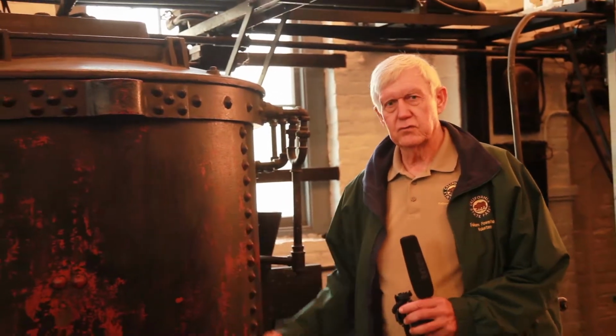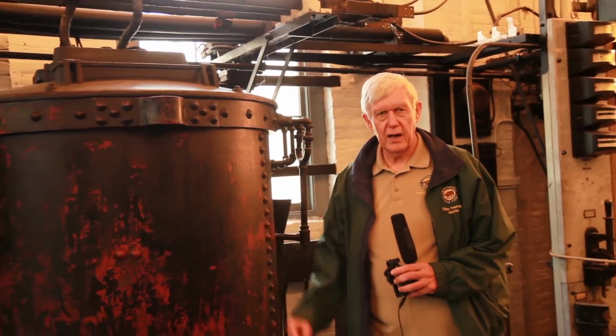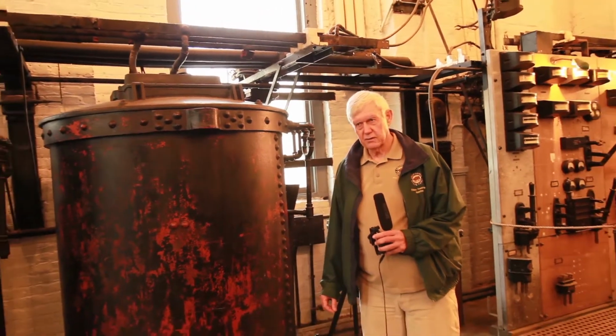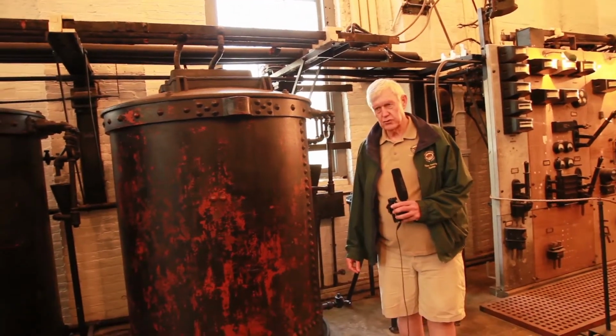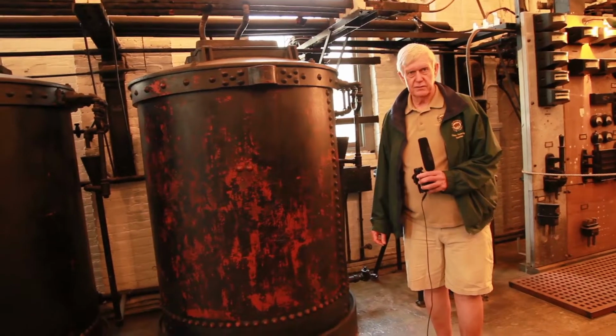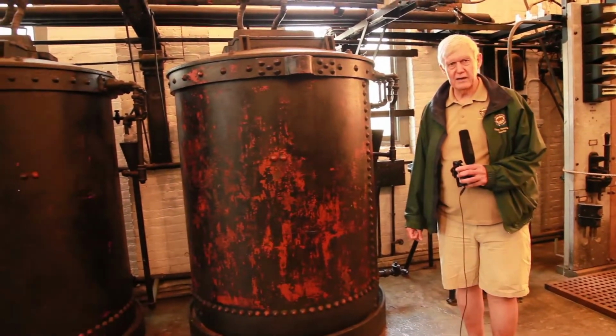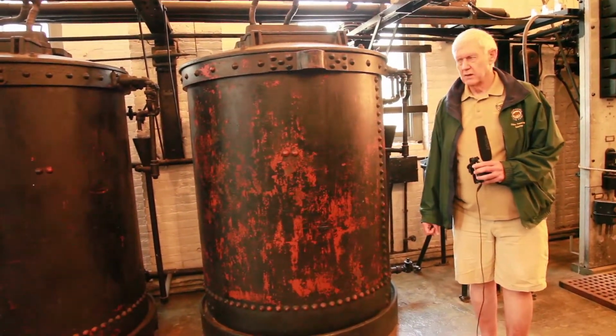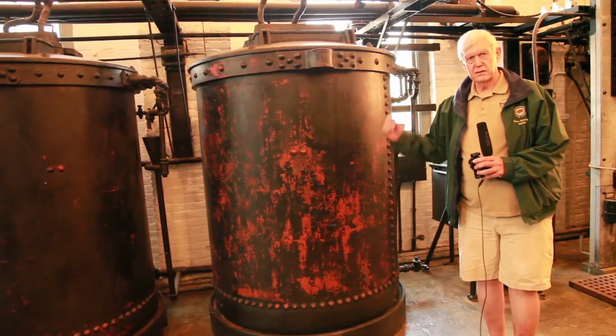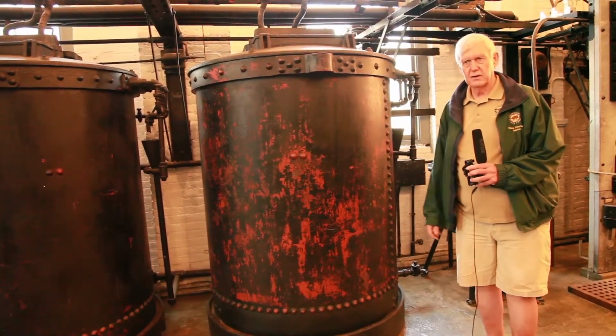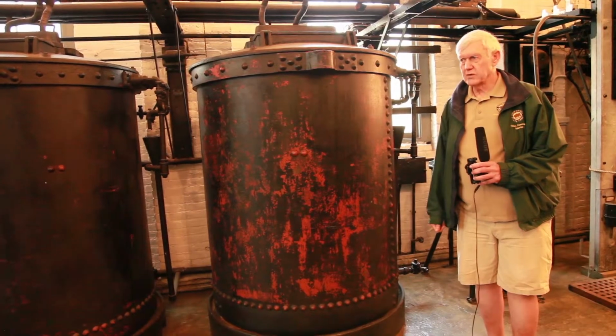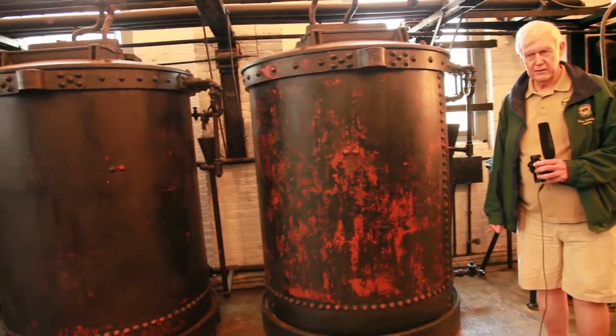The advantage of alternating current over direct current is that it can be run through transformers to raise the voltage way up high. With high pressure and high voltage, you can run current long distance. Here, it had to go 22 miles to downtown Sacramento. So these transformers and the air-cooled ones upstairs were capable of increasing the voltage from 800 volts up to 11,000 volts.